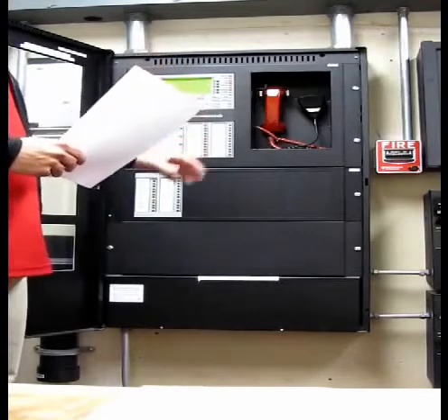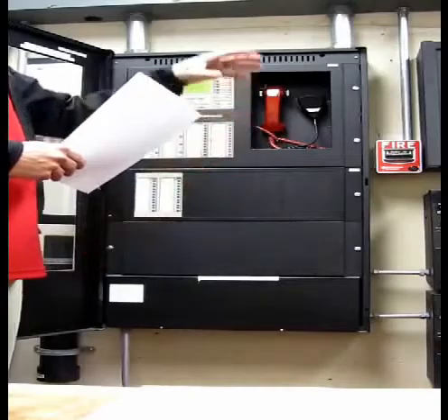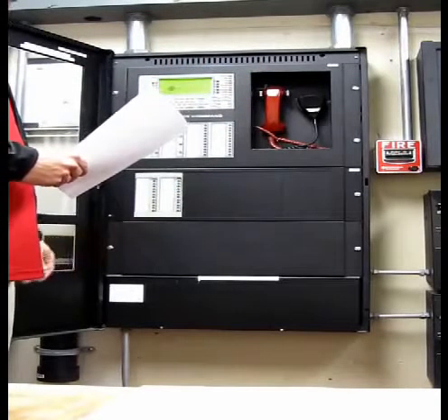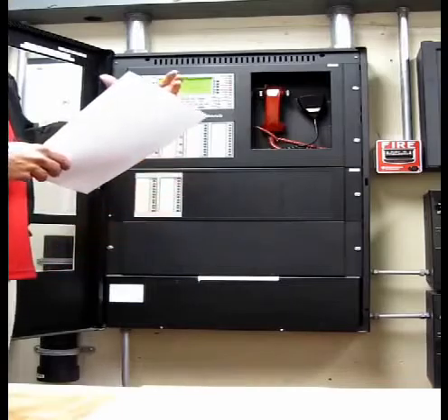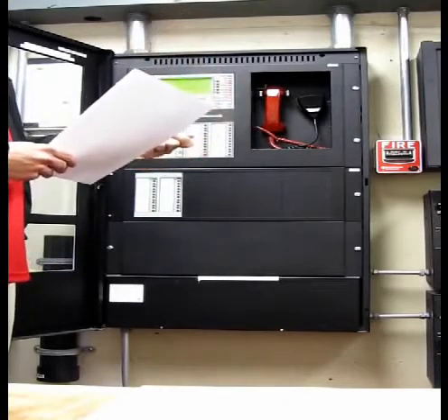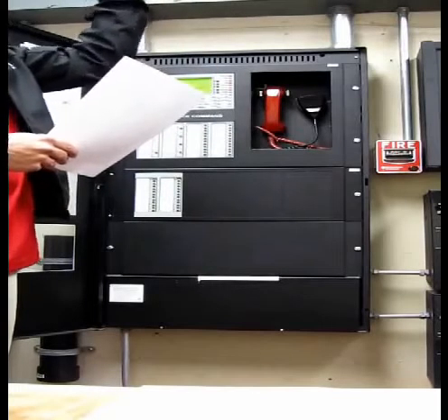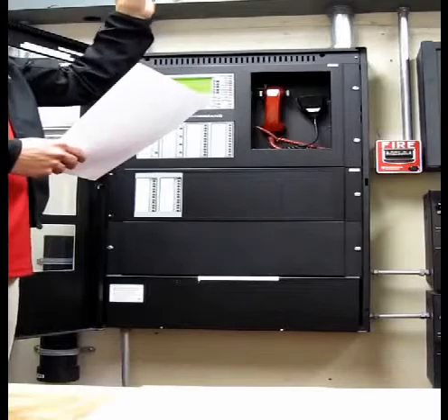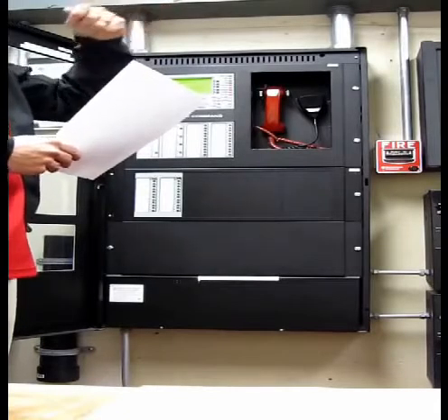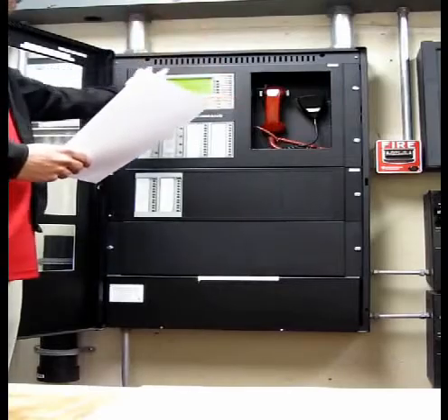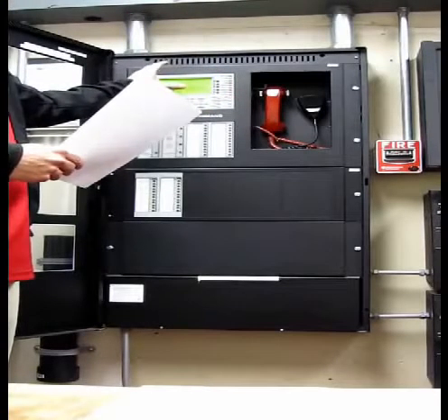The other major device that you guys have that's a supervisory device is all the smoke detectors in the guest rooms. And they're non-latching. So it's almost the same type of device as you have in your house. If there's smoke, if you guys are cooking or someone's smoking, the device will go off, with a local piezo on the base for the smoke in the room. And once that smoke is cleared, or the steam from the shower, that device will silence itself and it will reset itself on the system. So we call that non-latching.